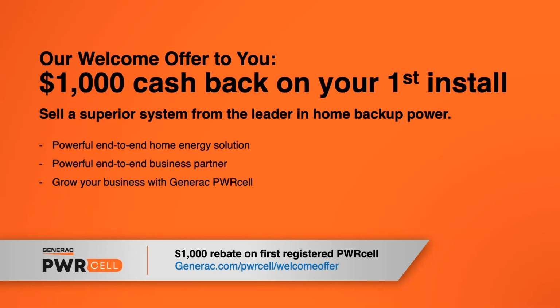But if you're oversizing the array on purpose because that customer is going to be cycling a full 6-module battery on a daily basis, that can make a lot of sense. The following day, say your battery's depleted down to whatever you set the reserve to be, that oversized array can then charge the battery and export to the house loads and the grid at the same time.